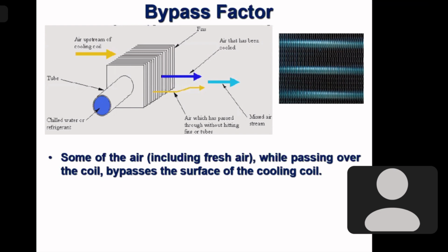Some air manages to bypass the cold surface and comes out totally unaffected. And the percentage of total air which comes out from the cooling coil totally unaffected is called the bypass factor of the cooling coil. In general, about 12% of the total air being passed over the cooling coil bypasses the cooling coil. So we call the bypass factor 0.12. Next.